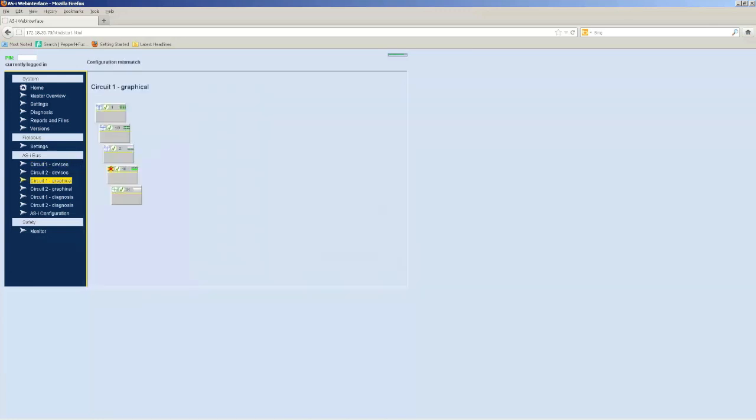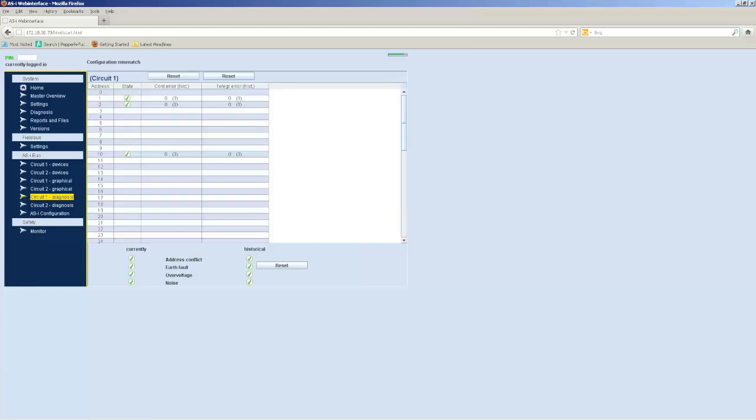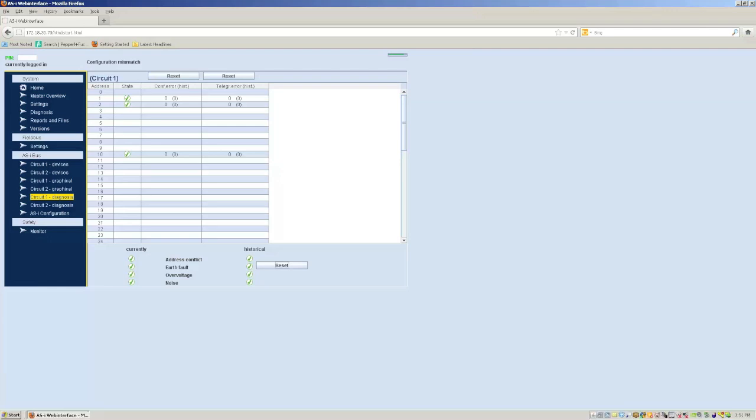You can also go to the Circuit 1 Graphical, if you want, and put these in a certain order on the network. They will stay there. Then, I like to go to Circuit 1 Diagnostics and reset the error counters, and let it run for 10, 20 minutes, and make sure that the error counters remain at zero. That means I've got a nice stable network, no problems, and everything looks good. And that should be all we have to do.